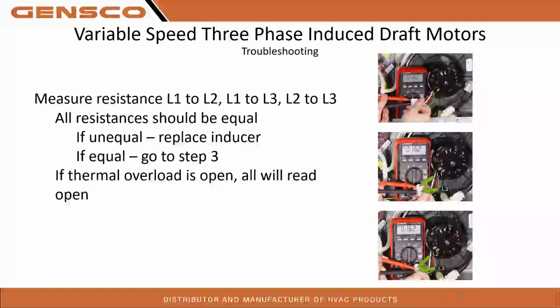These inducer motors hardly ever fail. Really, it's a 3-phase wrap, pretty simple. 3-phase motors are very simple inside. So usually not the problem, but definitely worth the check to make sure we've got an okay motor here. If equal, we're going to go to step 3. If the thermal overload is open, the motor's hot, obviously it should be very hot, all will read open. And I'll get back into the questions here towards the end, guys.